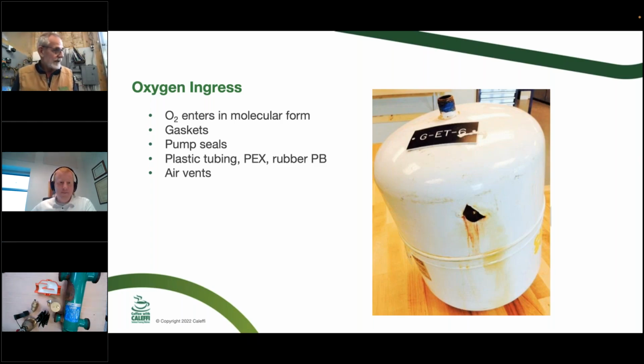And over here, this is a separator that was put in on a job. It was a rubber tube system that was put in 25 years ago, I think. This air separator was in the job for 18 months. And they got a call, and I've got a drip on the floor near my boiler, and this is what we found when they took it out. It actually pinholed, if you can turn a little bit there, Max, on the side, it actually pinholed right through the metal up there. I don't know if you can quite see it up by the port on the top, but a pinhole through that. Look at all the rust and deposit.